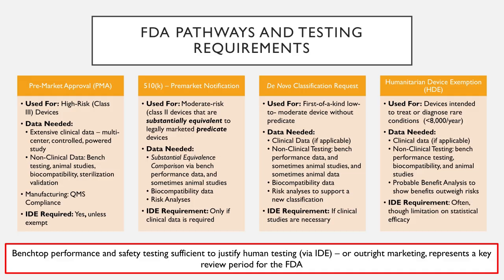So you might have to do clinical data if it's applicable to that particular device. Very often you can get away with just doing non-clinical, meaning non-human benchtop testing, sometimes animal studies or leveraging animal studies from other prior devices. You almost certainly have to do biocompatibility data. And then similar to the 510(k) pathway, certain risk analyses studies in order to justify the risk level of your device. If you do have to do clinical data, it's usually a much smaller cohort compared to a statistically powered PMA pathway. And if you do that, you do have to do an IDE.